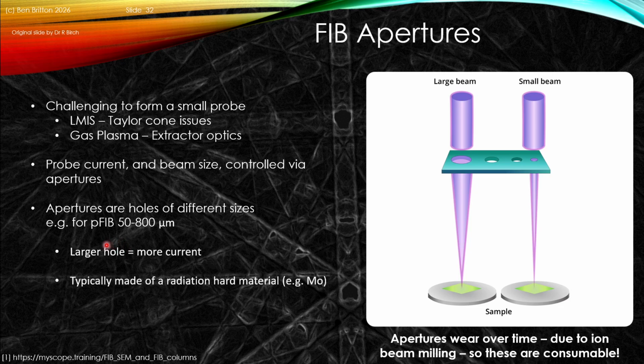There are a series of different aperture sizes depending on the specific setup. If you want to get into this discussion, I'd suggest that you talk to your manufacturer about more details. And these are larger holes to give you more current, and they're typically made of a relatively radiation hard material, something like molybdenum or tungsten in that mix.